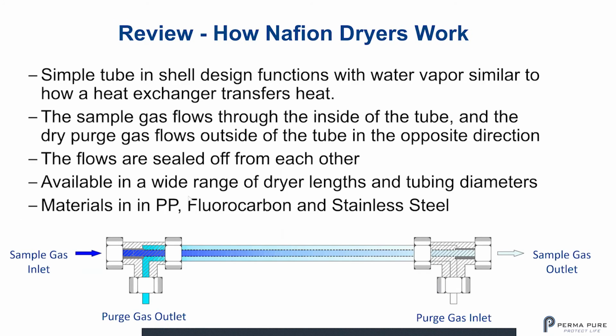So let's take a look at how Nafion dryers work. They are a simple tube and shell design that functions with water vapor similar to how a heat exchanger transfers heat. As you can see in the diagram, the sample gas flows through the inside of the tube from left to right, and the purge gas flows in the opposite direction from the right to left. The flows are sealed off from one another so they don't mix, and that purge gas is what strips the water from the sample gas. It is available in a wide range of dryer lengths and tubing diameters, basically to match the amount of water in the sample stream. And the materials are polypropylene, fluorocarbon, and stainless steel, depending on the corrosion resistance required by the tubing, or by the sample gas.